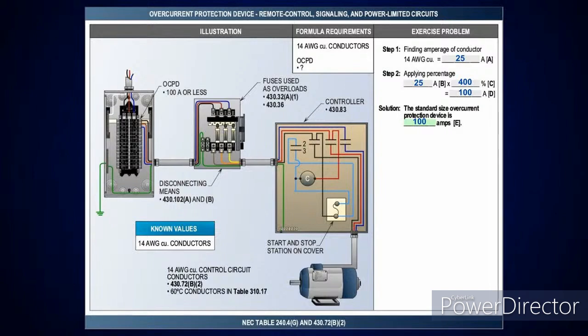Now, this one is where we're going to be looking at remote control, signaling, and power limited circuits. Basically you've got your control circuits inside the controller, and we're just cross-referencing, making sure that this is correct. So you're going to look through your code book at 430.72(B)(2). When you get there, you're going to see the table on that page, and it's got notes that refer you down. For this particular one, it refers you to note 2. It tells you it's based on 60 degree C conductors, but to look at table 310.17. And just remember this: these are control circuits, conductors that are inside the enclosure. That means it's in free air space. That's what table 310.17 is.